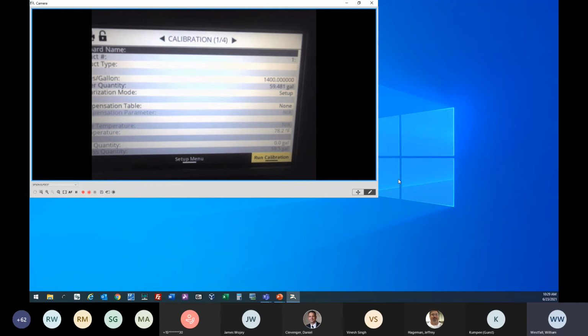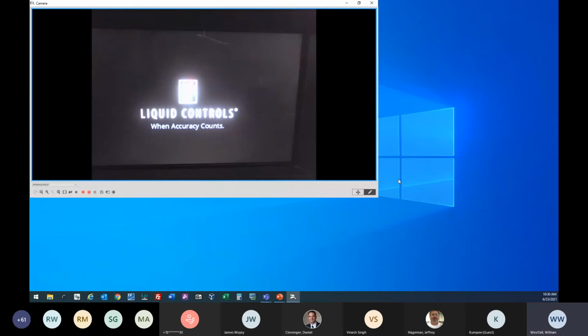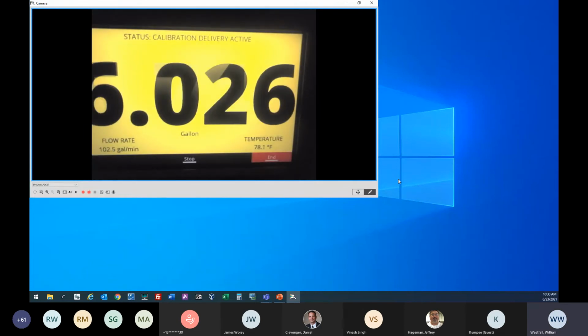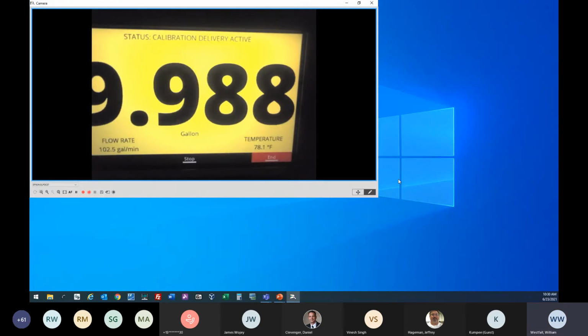Once we're in here, you can see we've got a lot of the same information. We've got our standard pulses per unit, pulses per gallon, 1400, so we've got a starting K factor in there. And here's our prover quantity field right below it. In order to start a delivery, you can see on the lower right we've got a button that says run calibration. So I'm going to hit the function key right underneath run calibration, and it's going to go to its delivery screen and start a delivery.